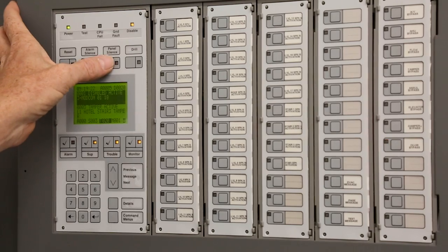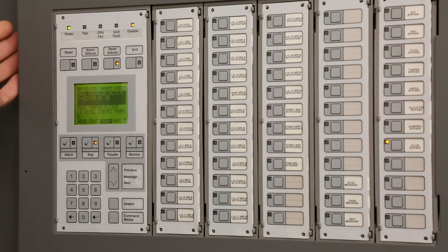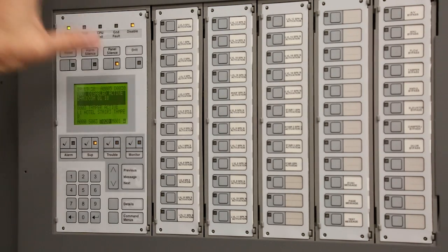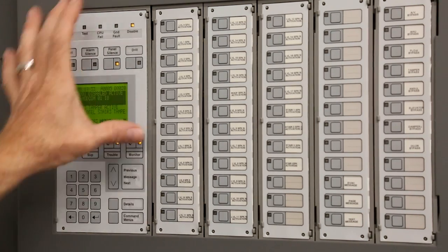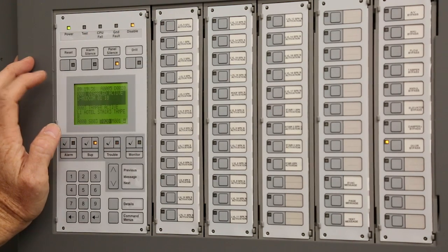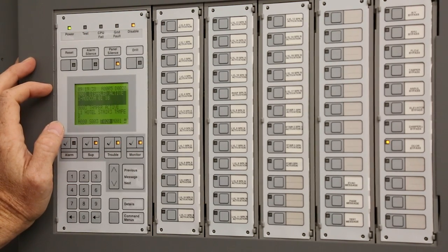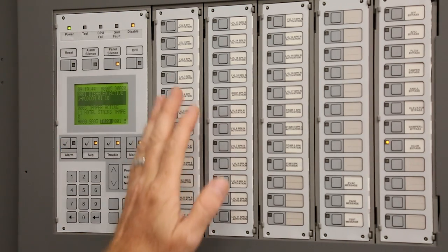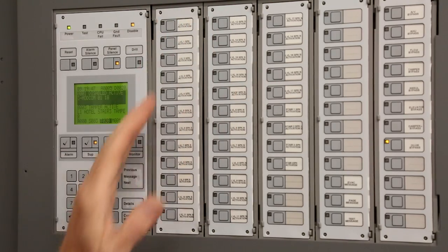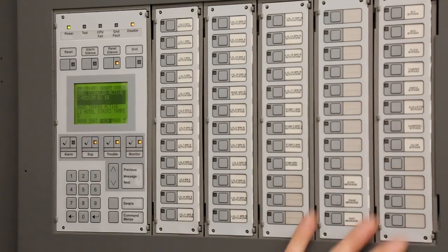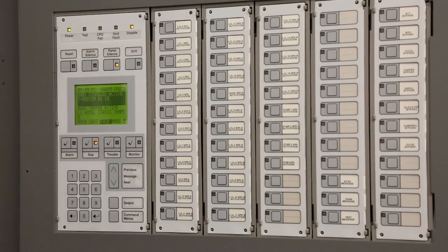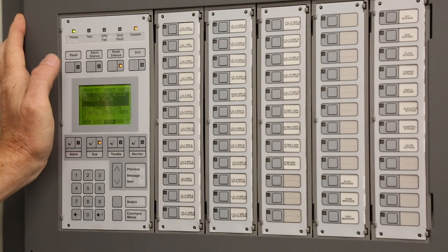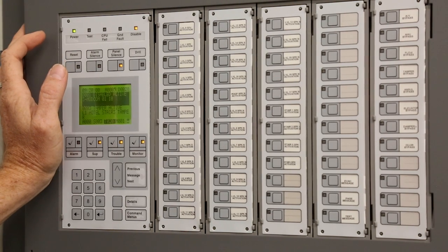We can hit panel silence here too. Panel silence basically shuts the panels up for the beeping because of the abnormal condition, and it will shut the local beeping up on any of these keyboards. This keyboard here is your main panel. We have a sub panel on the first floor north electrical room. It'll show the same display. Basically, just this portion right here will be shown over there. There are no bypass buttons or a microphone over there. But you have commands over there just like I'm doing here. You can silence it, you can reset and alarm silence from that location.